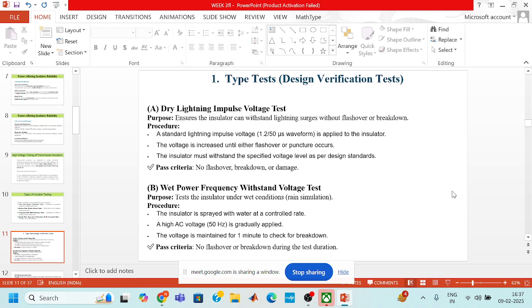The main procedure is that a standard lightning impulse voltage is applied to the insulators. Then the voltage is increased until any flashover or puncture occurs. The insulator must withstand the specified voltage level as per the design. So if there is no flashover, breakdown, or any damage, then the insulator will pass the dry lightning impulse voltage test.